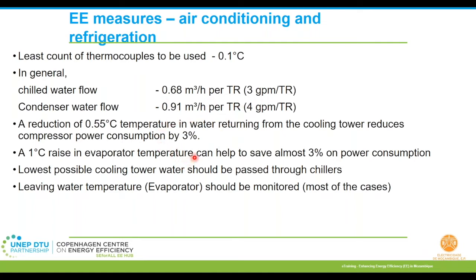And then again, generally you must be coming across certain slogans or drives that say, increase your set point temperature by certain degrees and do not maintain low set point temperatures, like not to maintain 18 degrees. Why not go to 21 degrees or 22 degrees as your air conditioning set temperatures and all, because this is the reason. So every 1 degree raise in your evaporator side or your set temperatures, you can actually save almost equivalent of 3% on the power consumption. So that way.